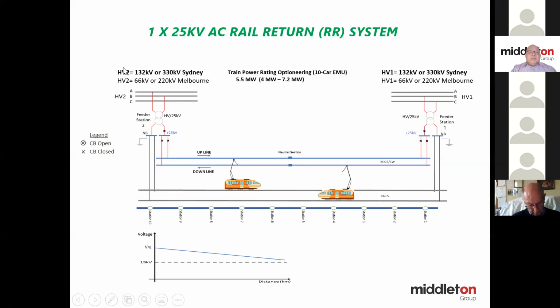So for this kind of system, you normally connect to a high voltage supply. In Sydney, we have 132 or 330. You can also connect to 66 kV if the supply is strong, but that's not preferable because it will introduce imbalance in the AC system, in the AC voltage. This is called negative phase sequence, which is a measure of the degree of imbalance that you're causing the AC system when you connect your load. So I'm using a 25 kilometer long railway. This could be our Sydney Metro, if you wish.